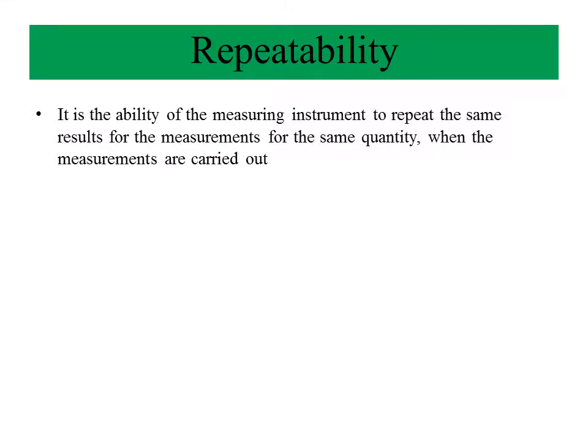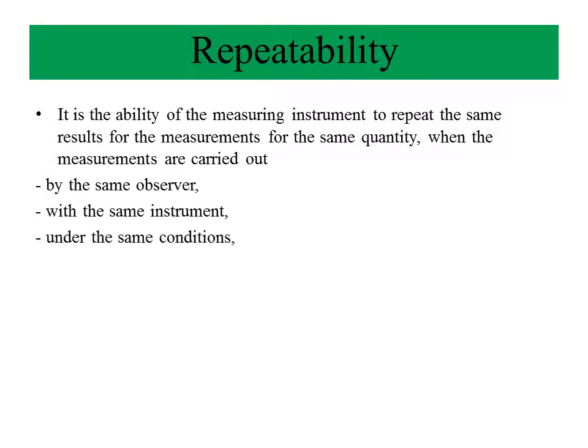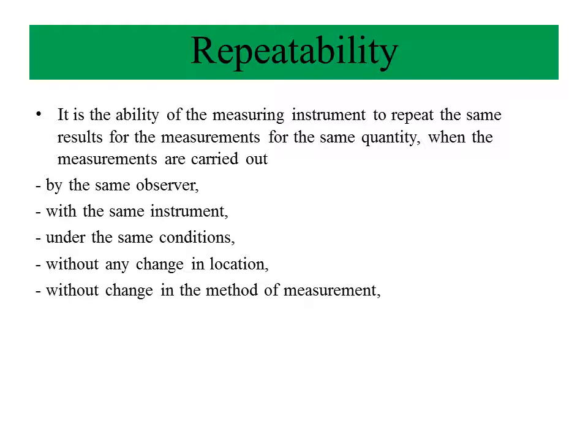Repeatability. It is the ability of the measuring instrument to repeat the same result for the measurement of the same quantity when the measurements are carried out by the same observer with the same instrument under the same conditions, without any change in location, without change in the method of measurement. The measurements are carried out in short intervals of time.